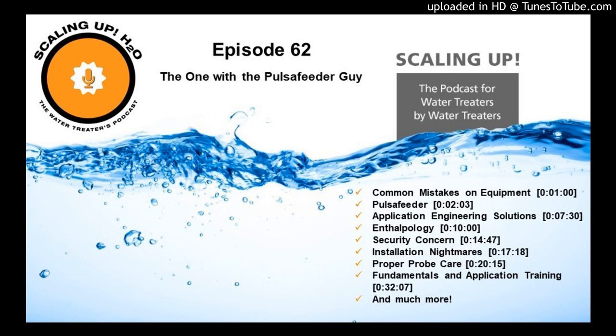Some people ship their panels that way, but that is to keep the probe wet should there be a no flow situation. I don't know if your piping drains in your process or not, but if it does, you definitely want a trap. You do not want those probes to dry out. Drying out is another recipe for disaster when it comes to early failure of these probes.